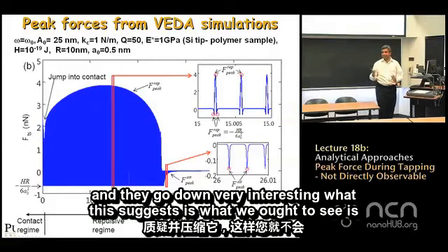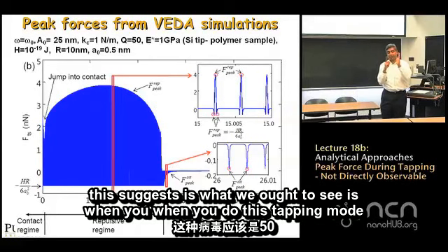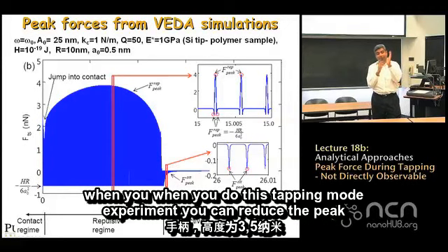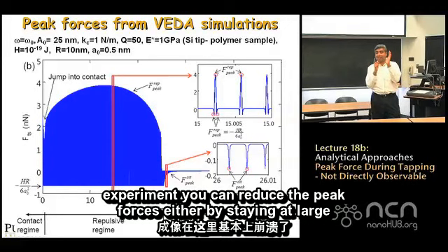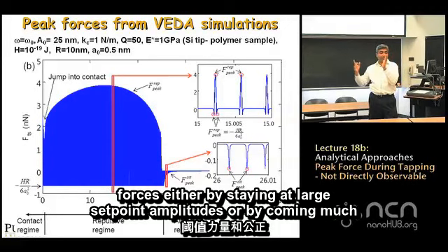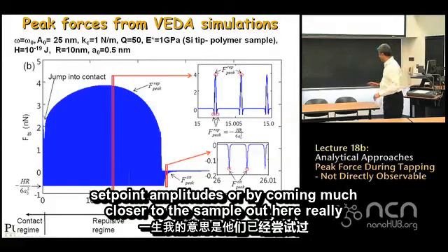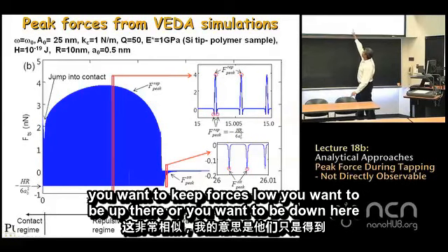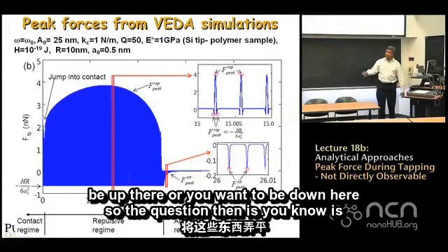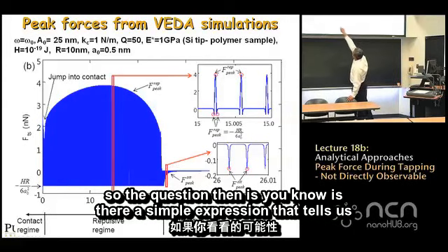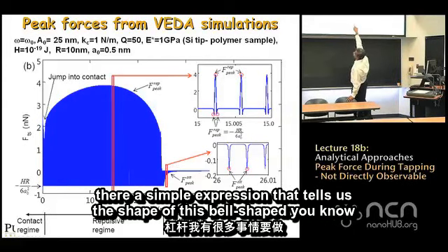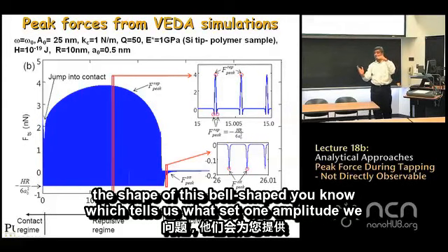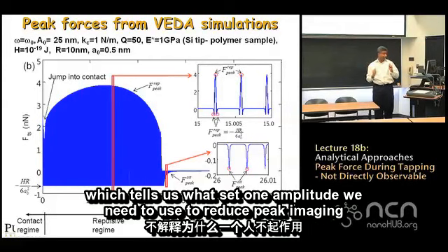This suggests that in tapping mode you can reduce peak forces either by staying at large set point amplitudes or by coming much closer to the sample and really reducing the amplitude. So if you want to keep forces low, you want to be at one extreme or the other. The question is: is there a simple expression describing this bell-shaped curve that tells us what set point amplitude to use to reduce peak imaging forces?